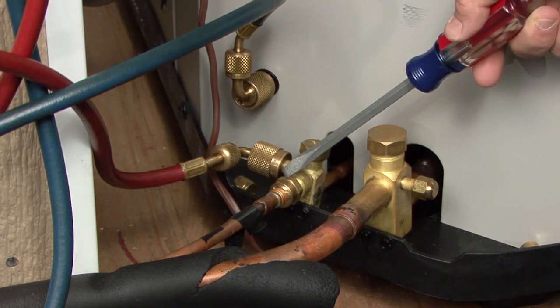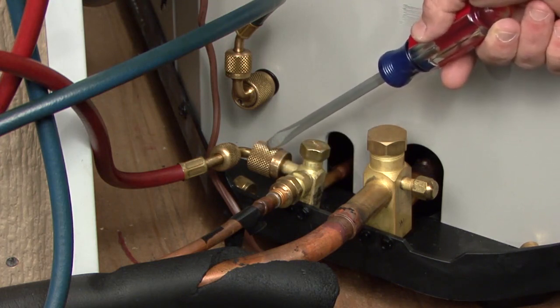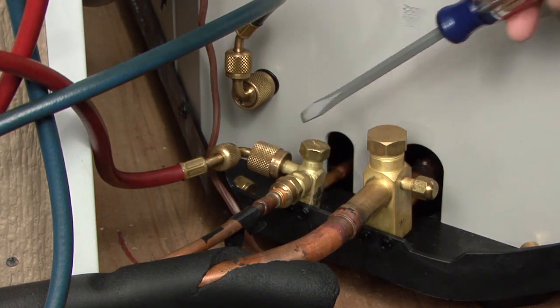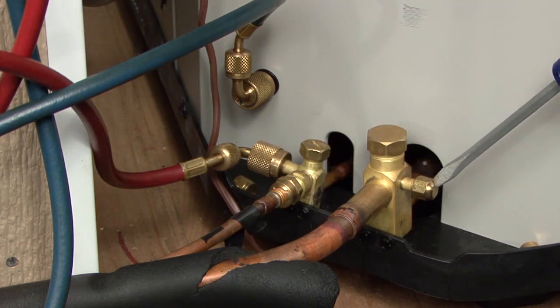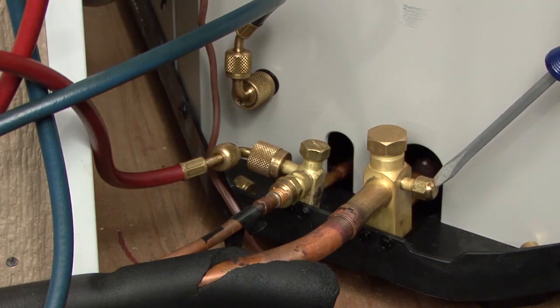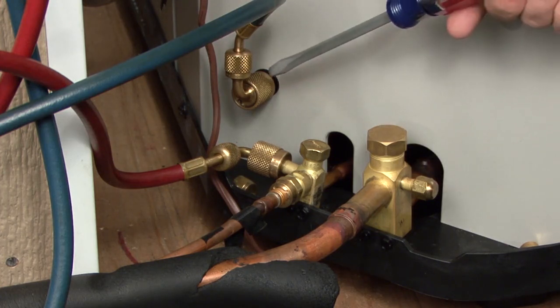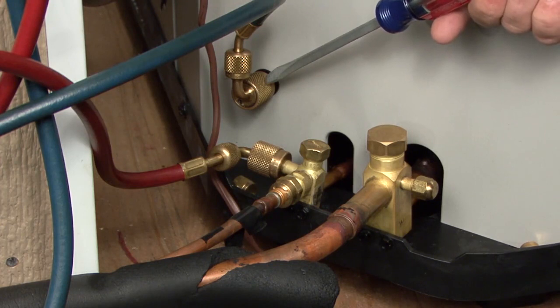we are going to need to take this red hose right here, and we're going to need to move it to the discharge line here, because this is no longer suction in the heating mode. This line is actually going to be high pressure discharge. So you put your high side hose there in heating mode, and your low side hose, you can still leave that on the extra port that we give you. Remember, that's always suction, heating or cooling.